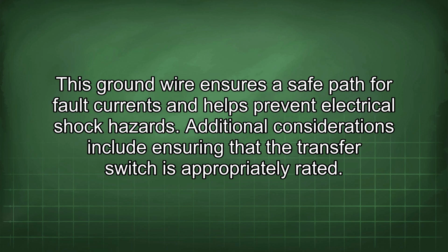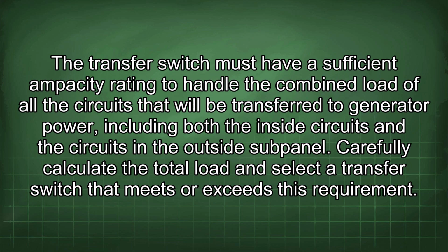Additional considerations include ensuring that the transfer switch is appropriately rated. The transfer switch must have a sufficient ampacity rating to handle the combined load of all the circuits that will be transferred to generator power, including both the inside circuits and the circuits in the outside subpanel. Carefully calculate the total load and select a transfer switch that meets or exceeds this requirement.